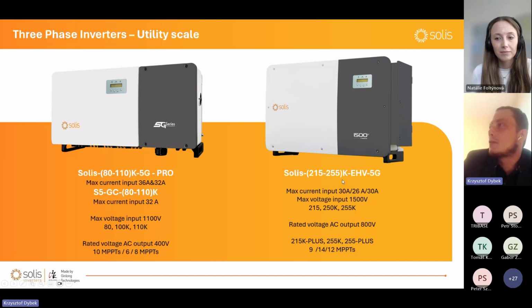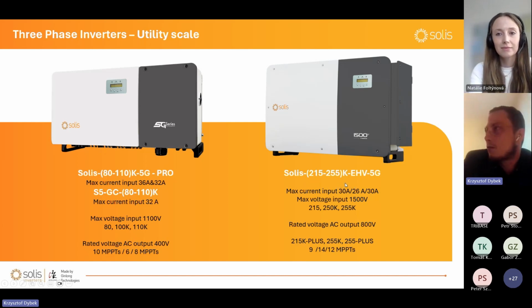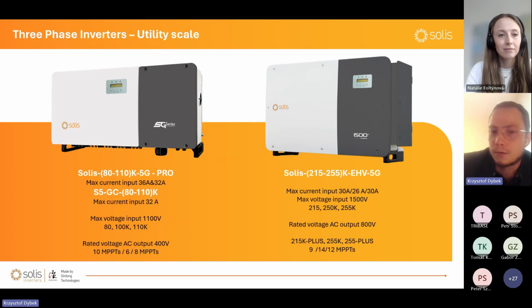And this guy is our biggest that we have released. We have an even bigger one, 350, but it is still under development. So let's focus on this guy. This is the biggest. Max voltage input is extended up to 1500 volts, and it works on AC rated output voltage of 800 volts. That's why we have high voltage in the name. The difference between the Normal and Plus versions is max current input, 26 amps or 30 amps in the Plus version.